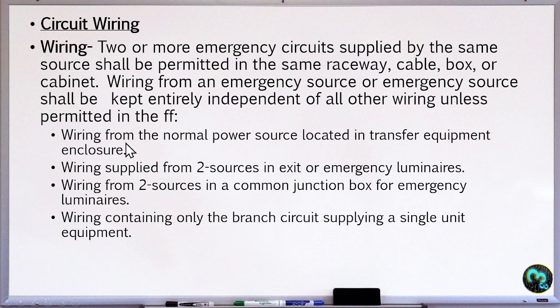First condition, wiring from the normal power source located in the transfer equipment. So we have a transfer switch, and the load side can be the same for the load of the emergency and of the normal system. Okay? Wiring supplied from two sources in exit or emergency luminaires. Wiring from two sources in a common junction box for emergency luminaires. And wiring containing only the branch circuit supplying a single equipment.